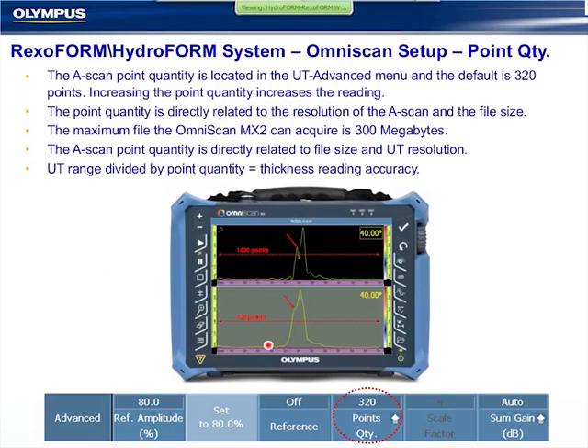So it's normal for these applications that we would increase the number of points in the A-scan. That is directly related to file size as well. Depending on the thickness accuracy that you need, you can dramatically improve or reduce your maximum file size by manipulating this. The file sizing capacity for the MX2 is 300 megabytes. I saw there were some MXU users in the attendees list, and unless you bought an optional larger hard drive at the time of purchase, most of those older OmniScans are limited to 160 megabytes.